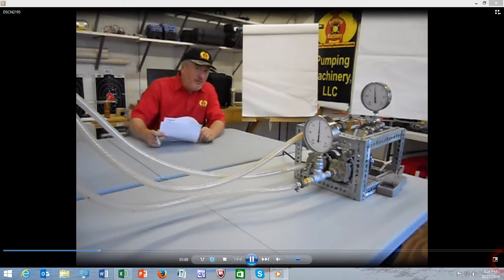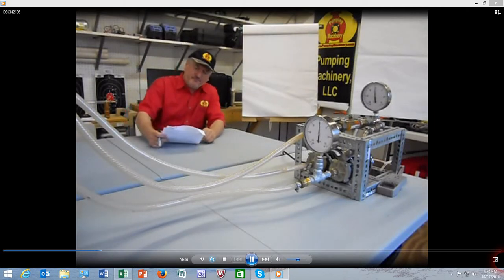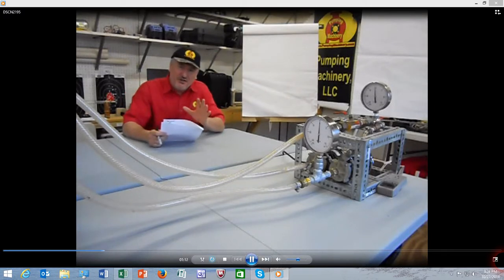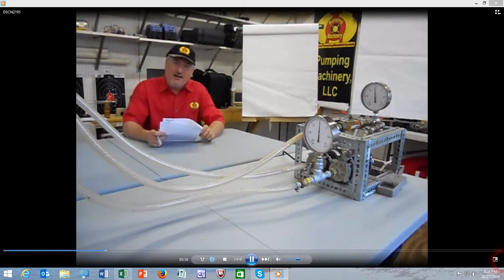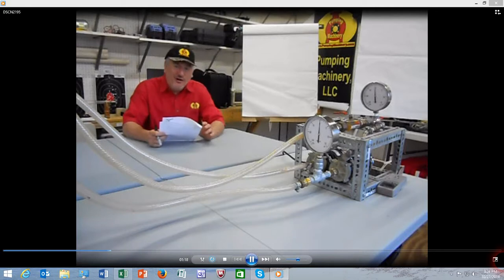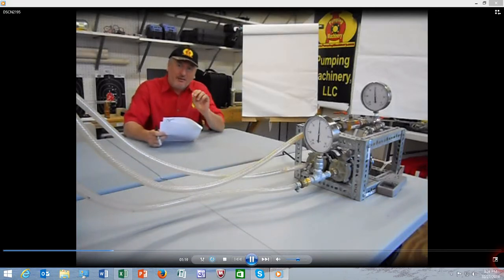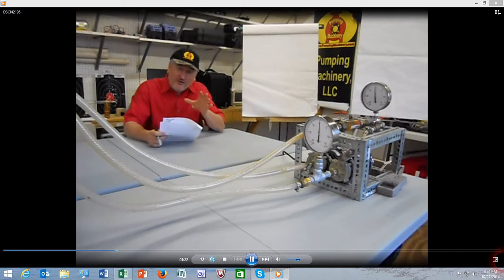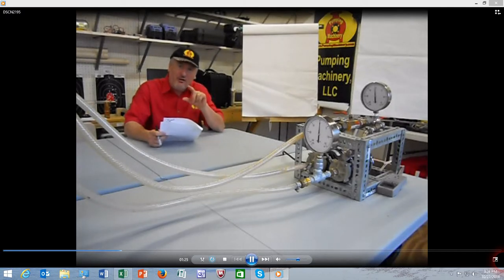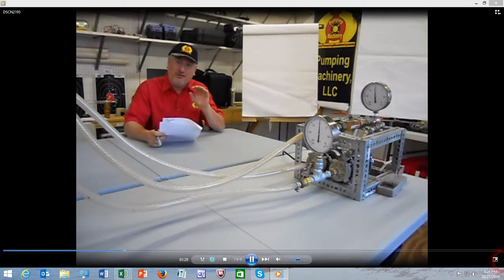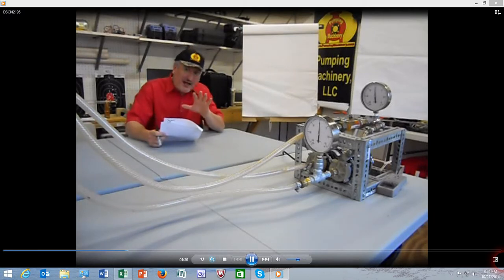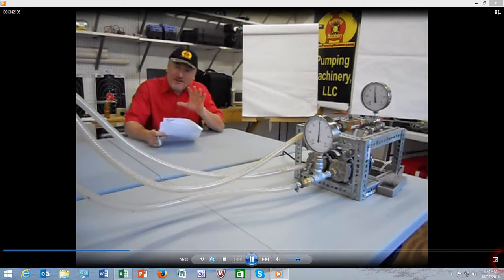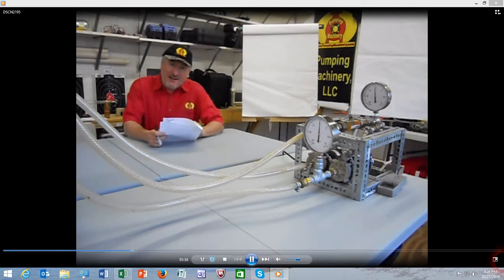Specific speed of the pump is often misunderstood, a little unclear concept. It actually has very little to do with speed limit or RPM. The formula is somewhat confusing: RPM times square root of flow divided by the head to the power 0.75. Don't ask me now why. That's a different topic. But that's the formula.